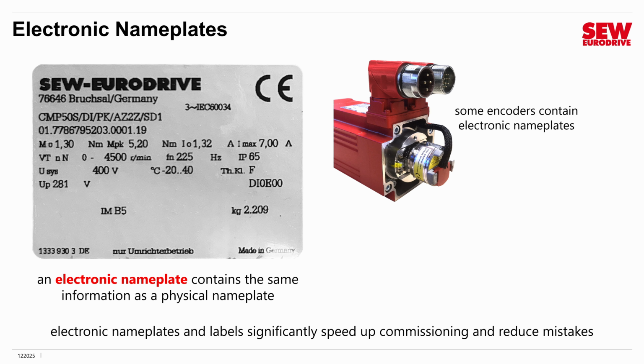Now, if you have just a standard physical nameplate, then what you can do is enter that information in when you commission the VFD. On the other hand, if you have an electronic nameplate or an electronic label, the VFD can read it automatically, which speeds up commissioning substantially. Now, electronic nameplates can live in two different places. One is in the encoder. Some encoders include an electronic nameplate, some don't.